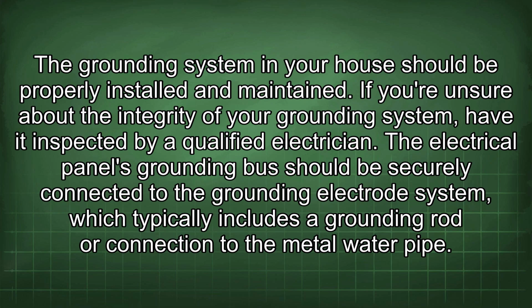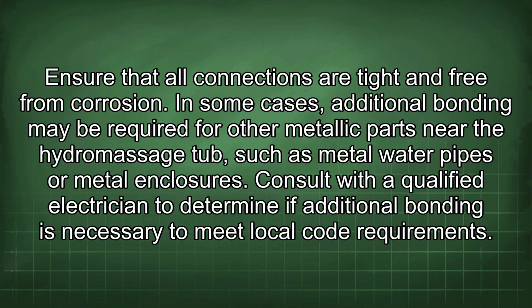The electrical panel's grounding bus should be securely connected to a grounding electrode system, which typically includes a grounding rod or connection to the metal water pipe. Ensure that all connections are tight and free from corrosion. In some cases, additional bonding may be required for other metallic parts near the hydromassage tub, such as metal water pipes or metal enclosures. Consult with a qualified electrician to determine if additional bonding is necessary to meet local code requirements.